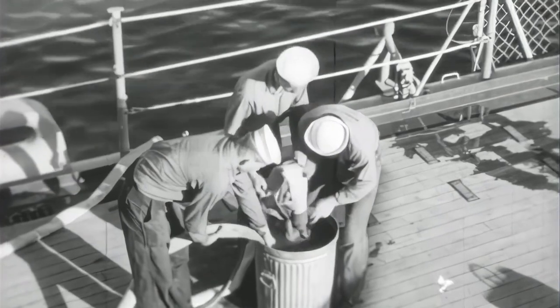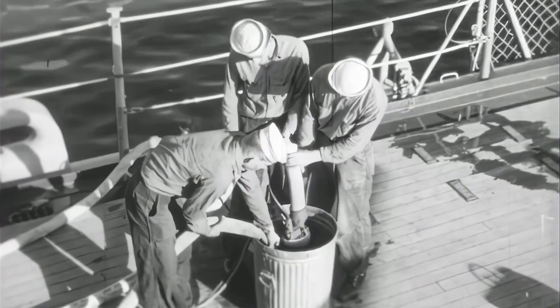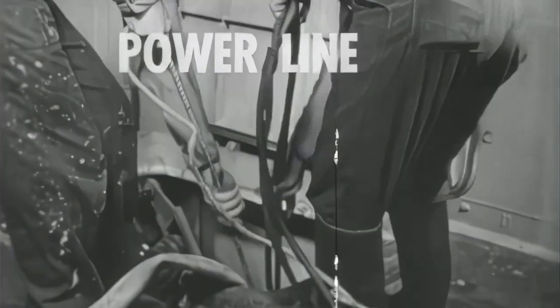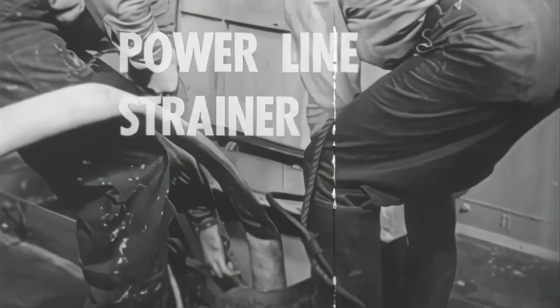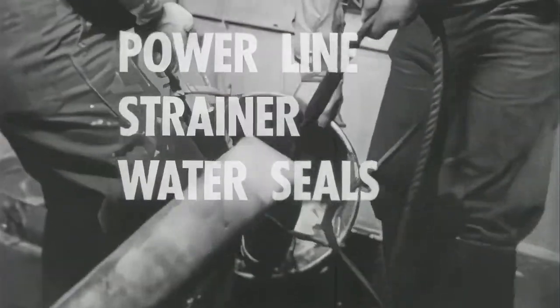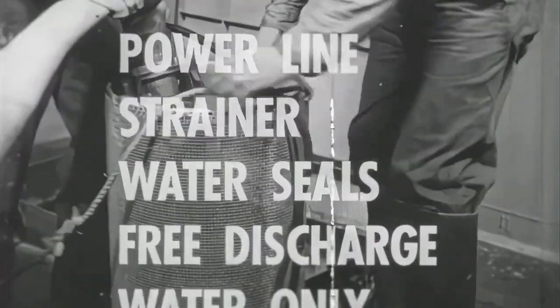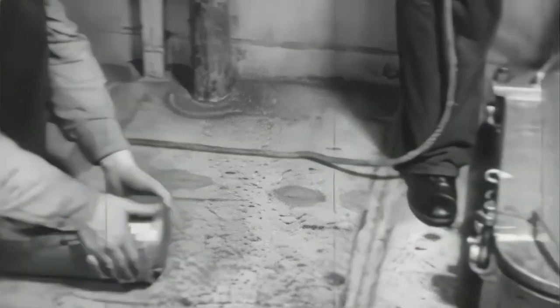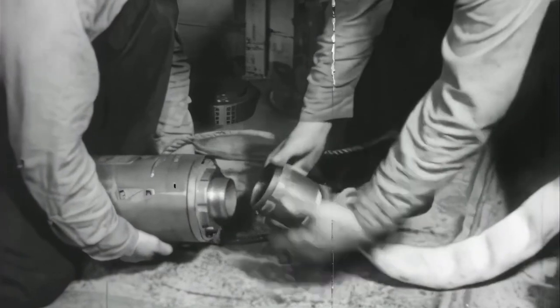Every portable pump on the ship should be tested once a week; an ordinary trash can may be used. An electrician's mate should go over the wiring frequently. The limitations of portable electric submersible pumps: the power line should never be used in handling or lowering the pump; a basket-type strainer should be made for each pump; the water seal should be checked frequently and replaced to avoid short circuits; a free discharge must be maintained and nozzles should never be used; the pump should be used for water only, as other liquids such as oil and gasoline will impair proper cooling. For heads over 50 feet, the discharge from one submersible can be connected to another at a higher level — this series hookup may solve an otherwise tough problem.